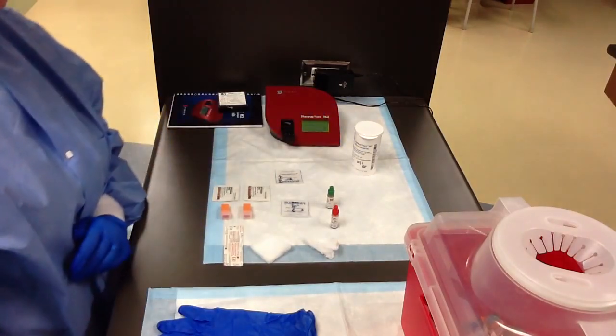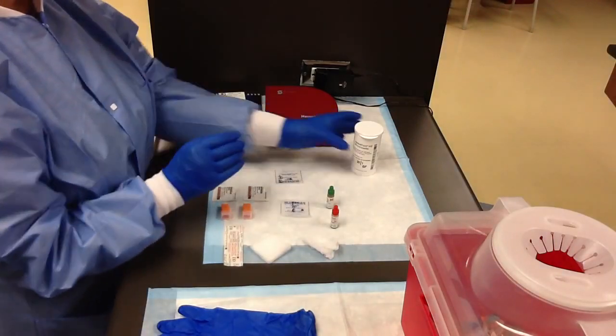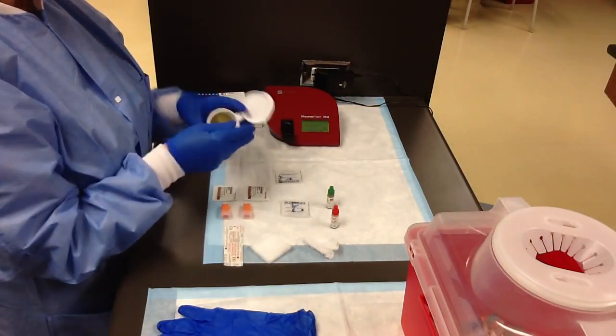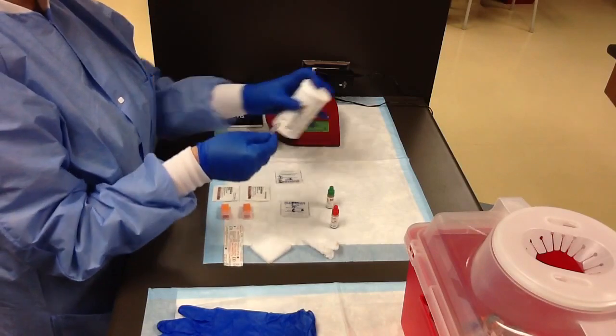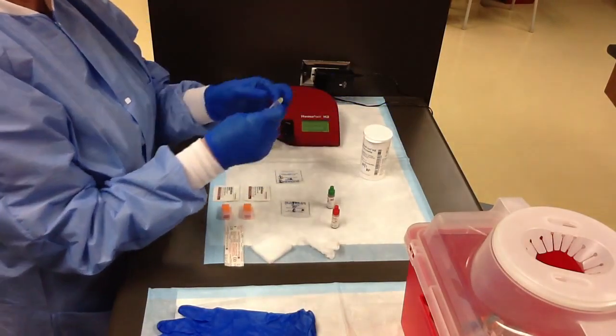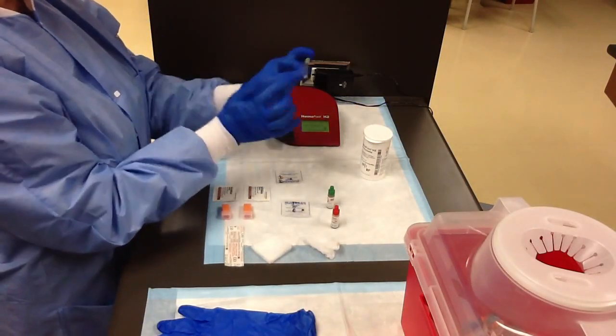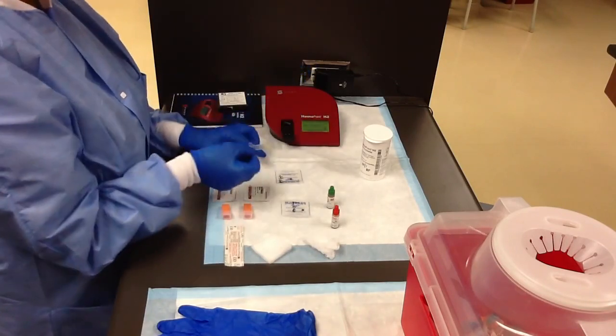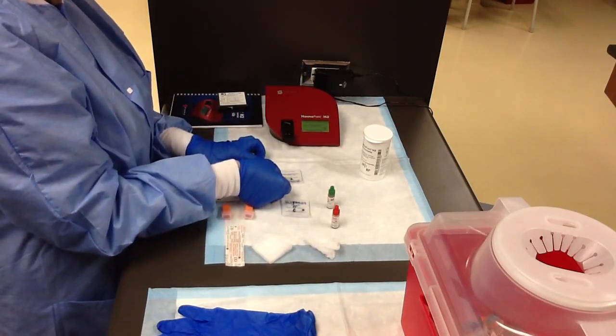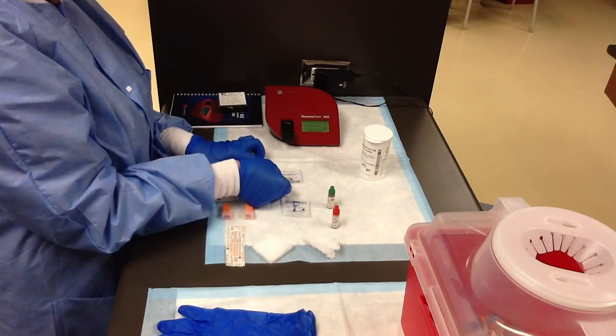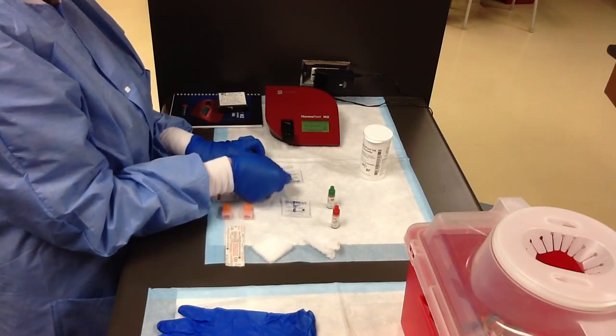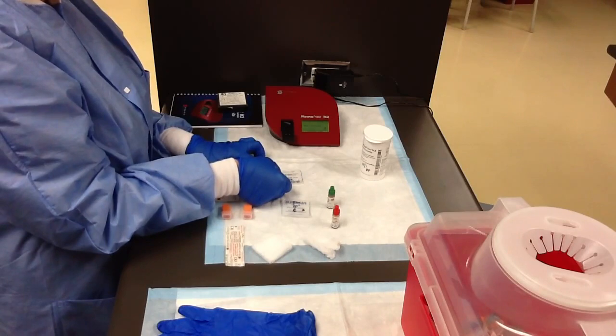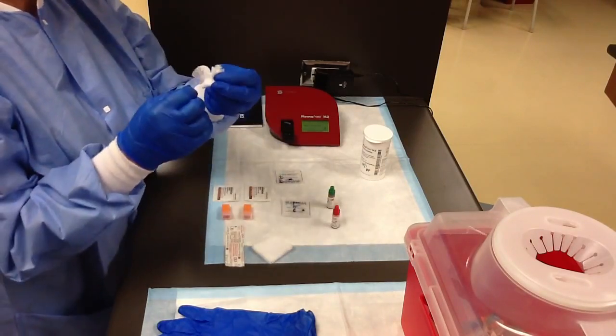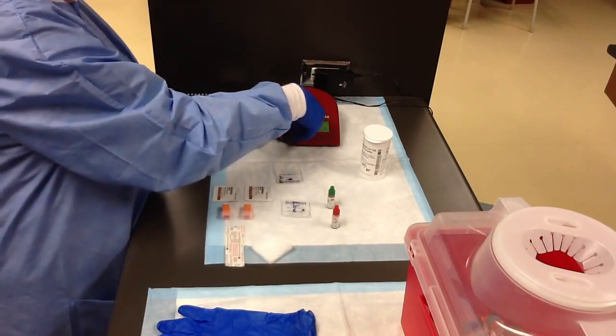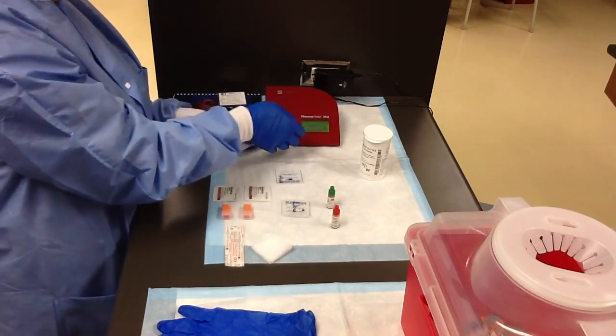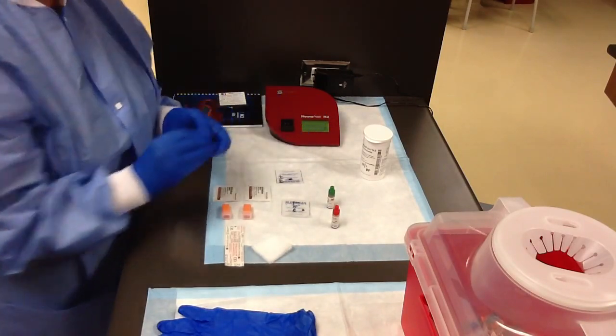I'm going to record the result, and then I'm going to come back and run the high control. Once again, I'm going to make sure the cuvette is in the right orientation. I'm going to touch it to the drop of control. It's going to fill by capillary action. And then I'm going to wipe the bottom. I'm going to insert it in the machine and manually close it.